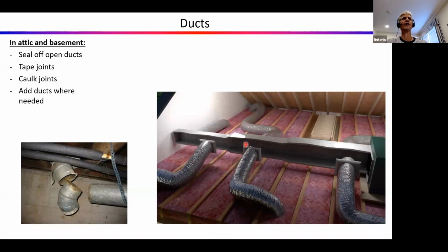The delta T is higher in the ductwork, and ducts tend to be leaky. It's a terrible situation, and it really should be against code, but unfortunately it's not. Insulation codes should require more insulation on ductwork than between the building and the attic.